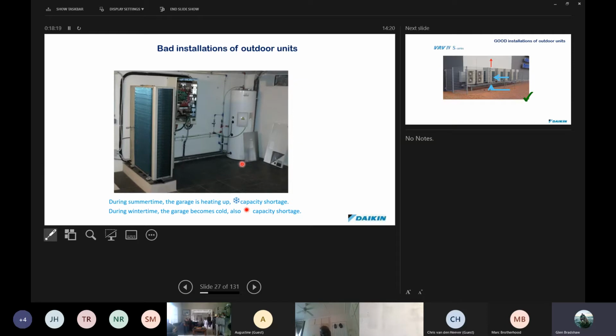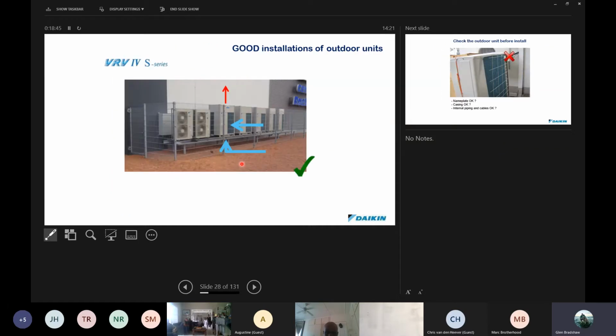Okay, so there's just some considerations to make. These are common mistakes that we come across. And it's just something that the guys need to move away from. Obviously, we know that it's very difficult for the installation technician, but it is something that project managers need to just negotiate a bit stronger. And that we're using units that are of the highest efficiency, and we mustn't do things that act against that efficiency. Okay. Good installation, view this one over here. Okay, and over here we can see we've got a mixture of units. They've put a fence around it. Obviously, that's for security and for safety as well. We've got free-flowing access air, both underneath the units and in through the side, and free discharge out the top with no chance of recirculation.